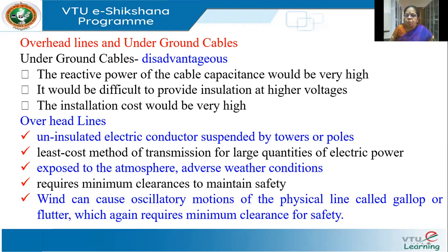However, underground cables have some disadvantages. Cable capacitance is very high, and if capacitance is high it will draw a heavy charging current. This restricts the underground cable to around 15 kilometers — you can't have it for longer lengths because of excessive heating, the Ferranti effect, and very high receiving end voltages. So we can't have it for very long distances.